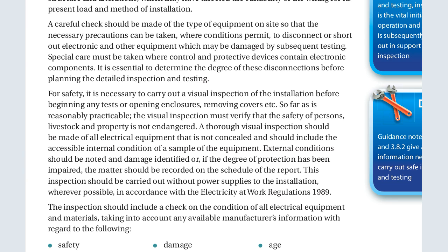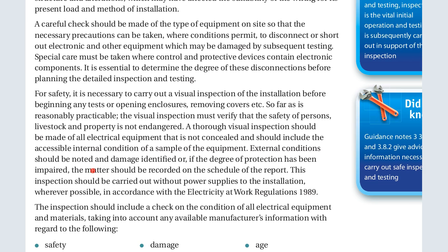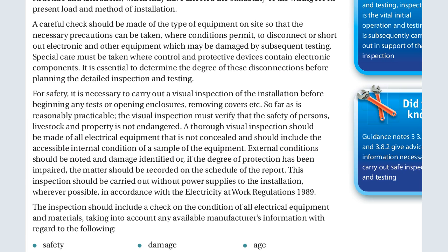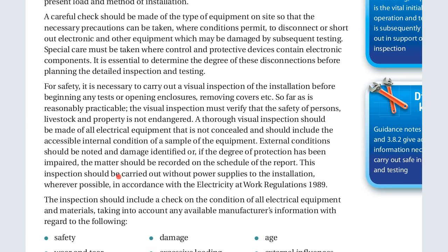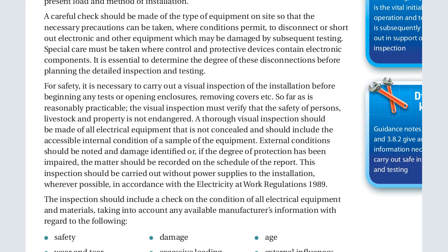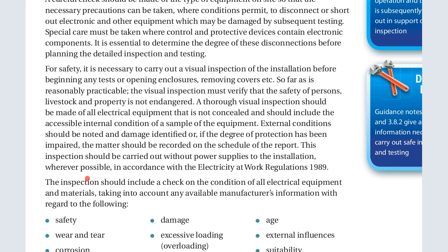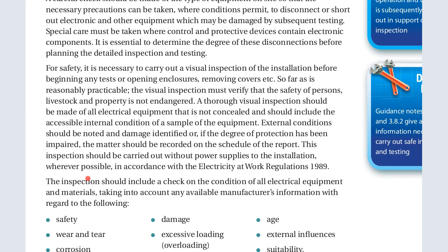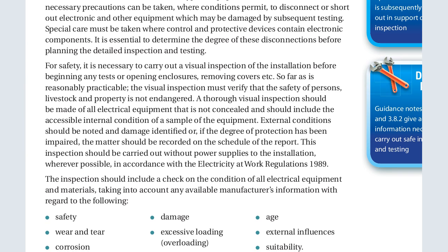So far as is reasonably practicable, the visual inspection must verify that the safety of persons, livestock, and property is not endangered. So a thorough visual inspection should be made of all electrical equipment that is not concealed and should include the accessible internal condition of a sample of equipment.